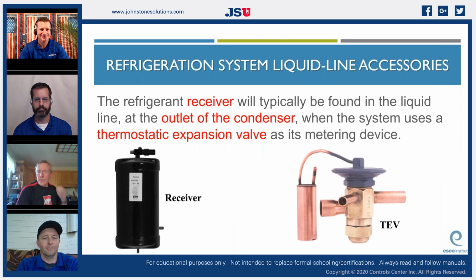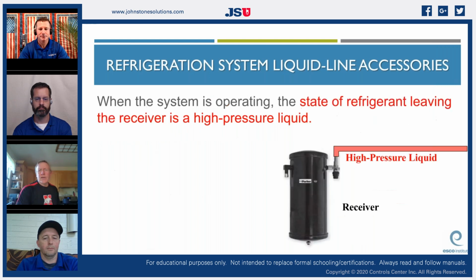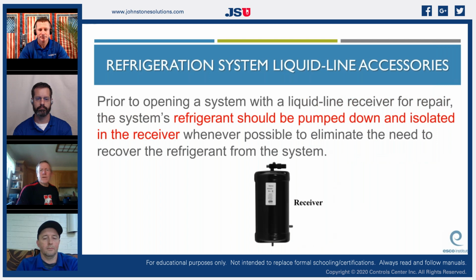The refrigerant receiver is typically found in the liquid line at the outlet of the condenser. It's a high pressure liquid in the receiver. It should be pumped down and isolated in the receiver. A lot of times when we pump a system down, we make the condenser the receiver, and it accepts all the refrigerant as it came from the factory in the first place. So not all equipment has these receivers, by the way.